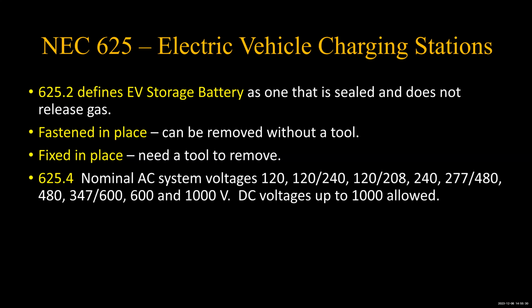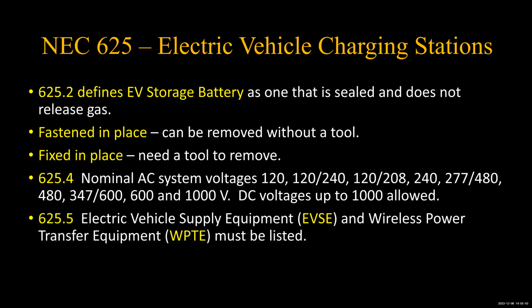625.4 says that these are the nominal AC system voltages that you can use for an EV charger, all the way up to 1,000 volts for AC, and you can also go up to 1,000 volts DC. EV supply equipment, EVSE, and wireless transfer equipment.